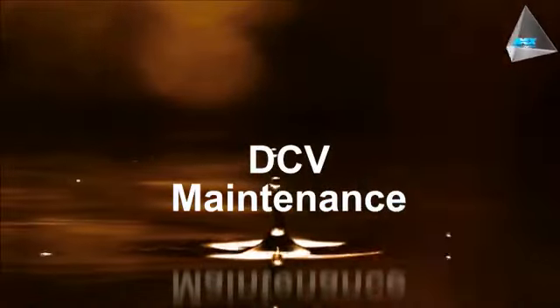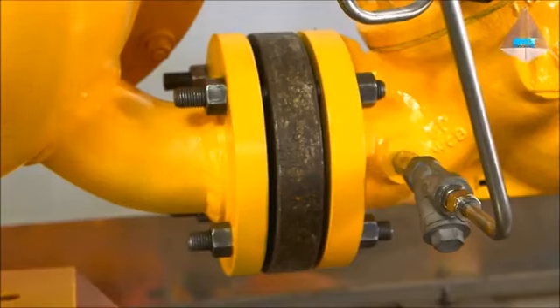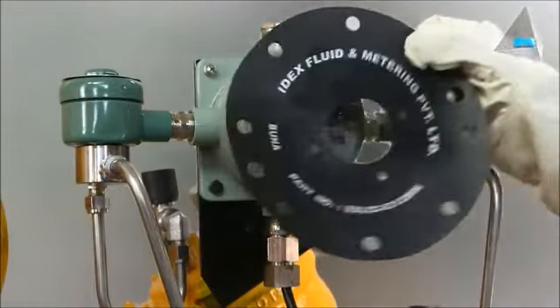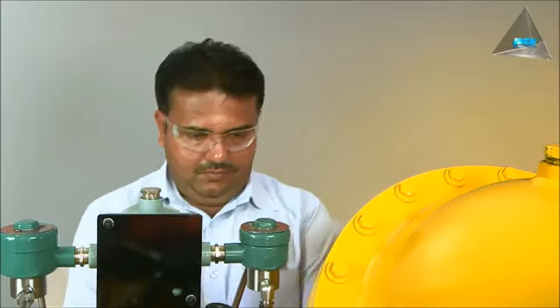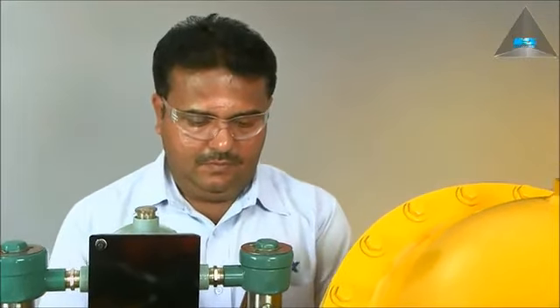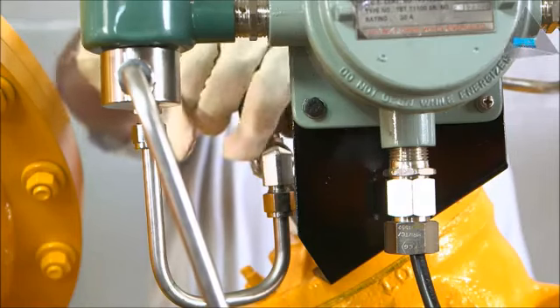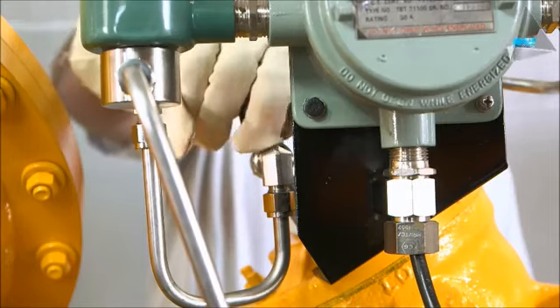DCV maintenance. Check the strainer, solenoids and diaphragm after initial setup for any accumulation of debris or movement, and clean as appropriate. Needle valve needs to be locked after tuning or speed setting.